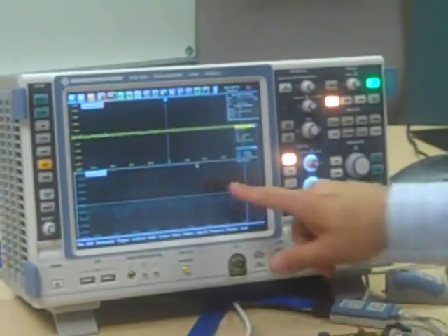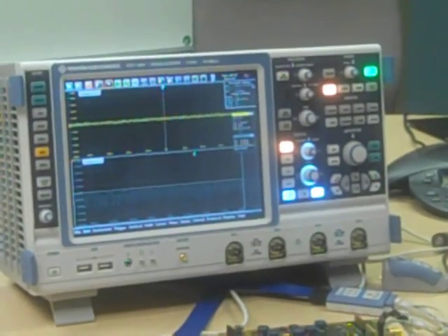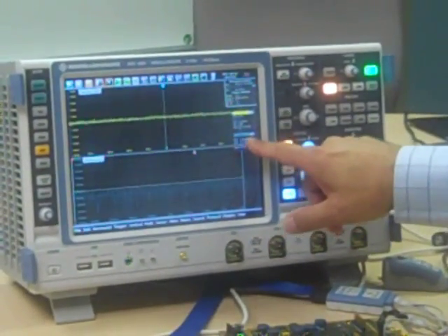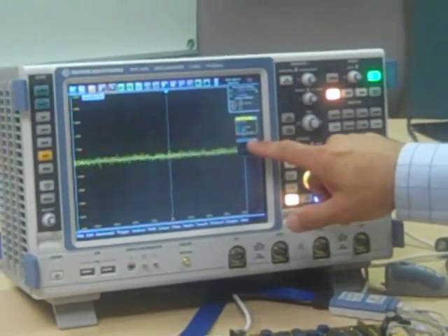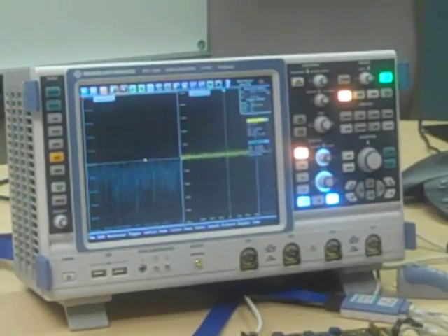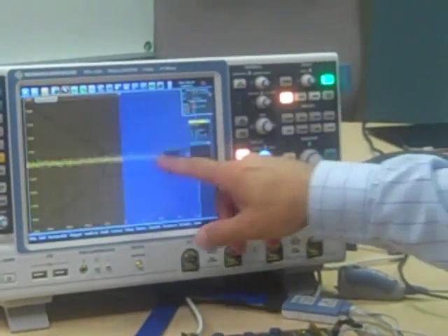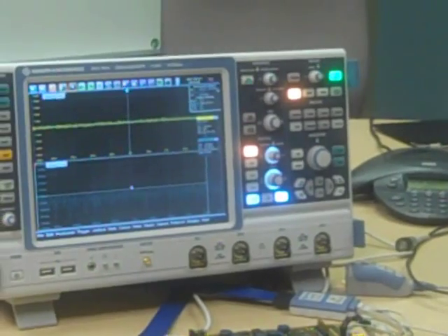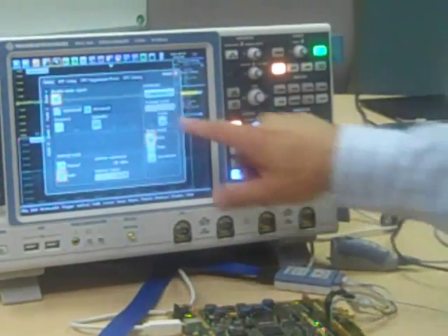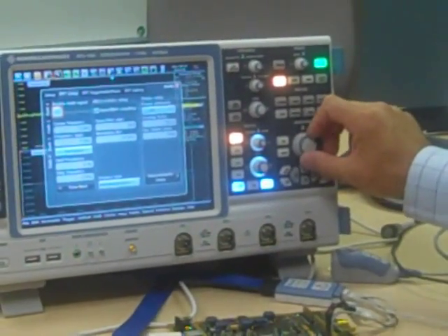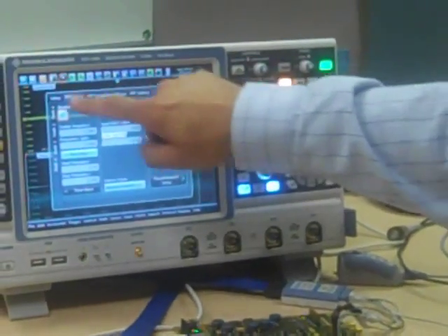We can take a quick look at the FFT by touching the FFT tool. Now the FFT is shown in the graph below, and the graphics on the screens can be controlled by touching on this toolbar and sliding the diagram to wherever you want it, so you can split the screen in multiple different ways, top, bottom, or side to side. We're going to adjust the FFT resolution bandwidth control so that we have some more fine detail and frequency, and I'll do a little averaging on that.